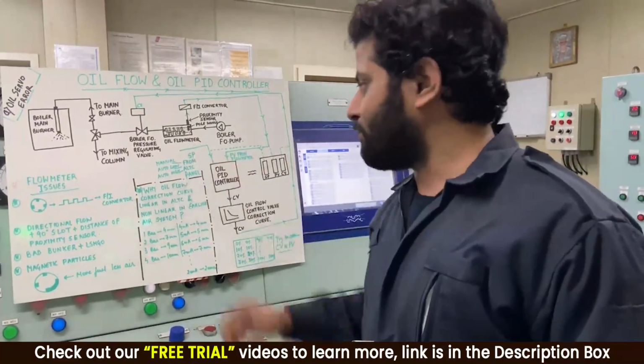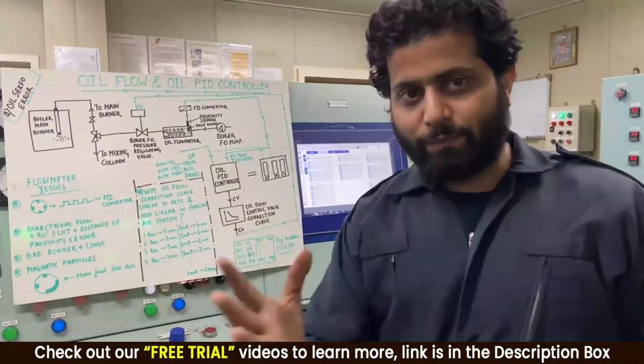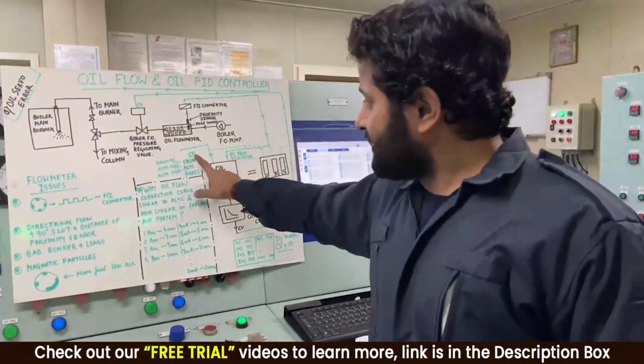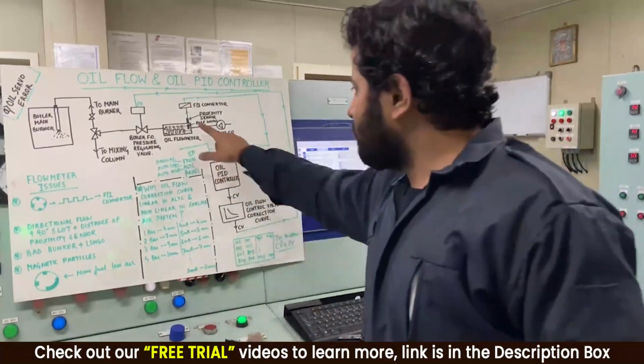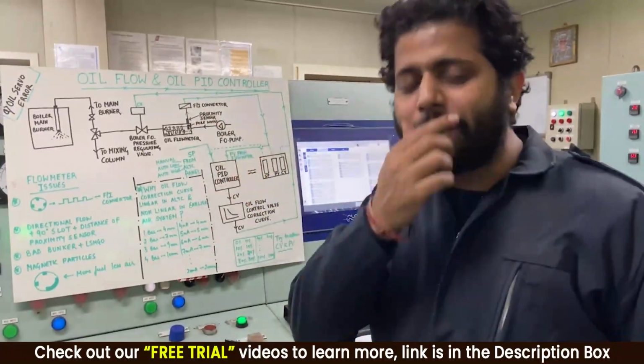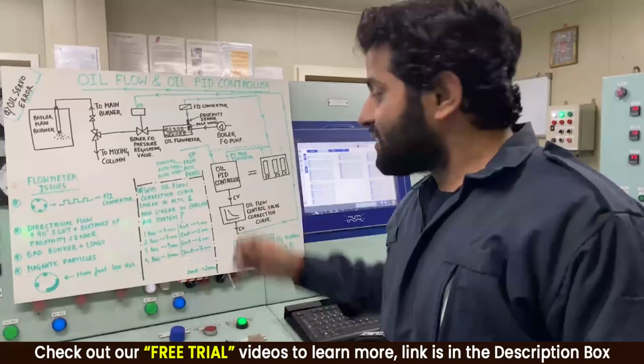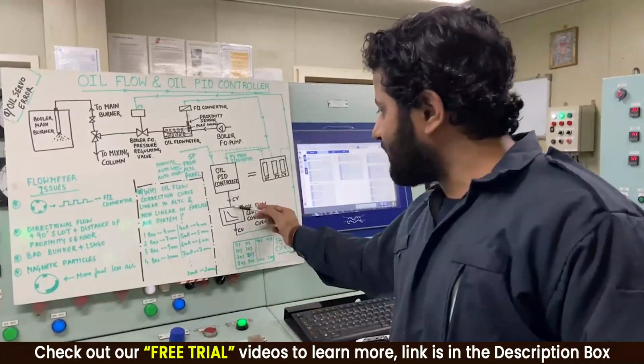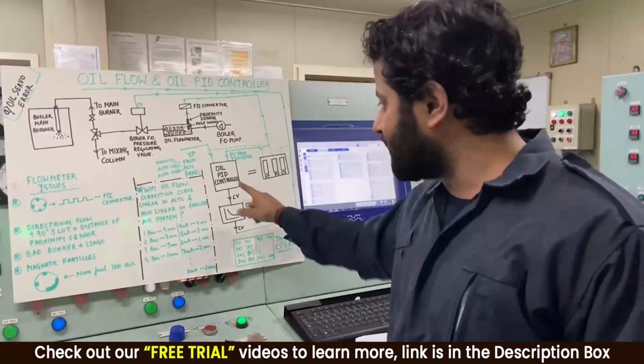So I have got a set point. Say I want load to be 25%. Process value is coming from over here. Now say set point is 25%. The flow meter says, "Hey, right now the flow is only 20%." So there is a difference between the set point and the process value, and a CV is generated. An output signal is generated by the controller.